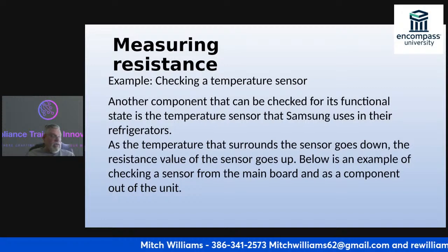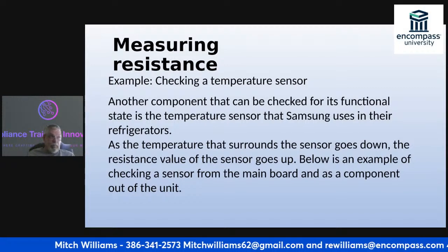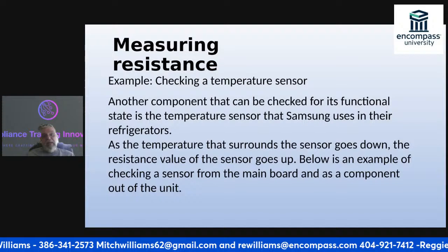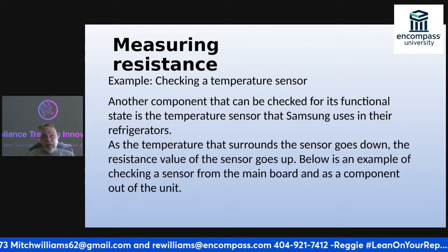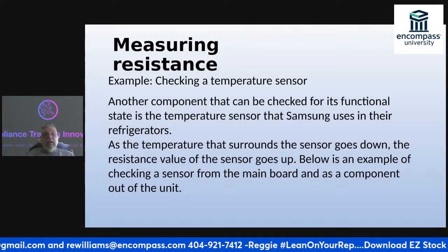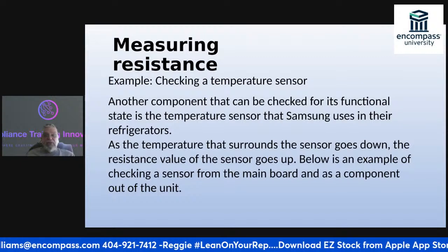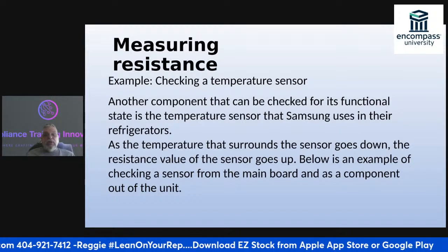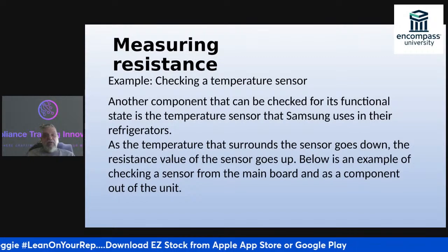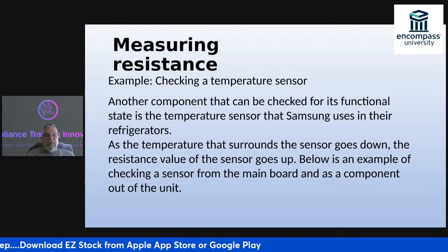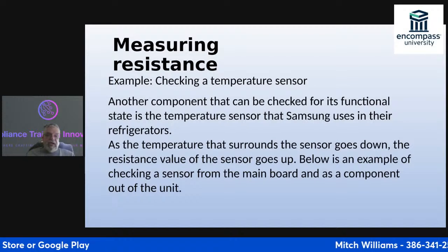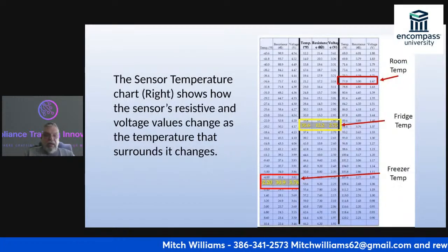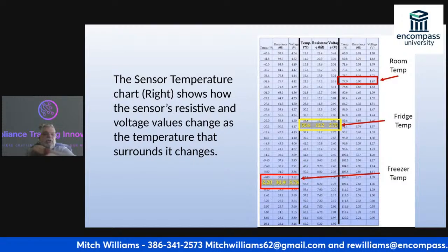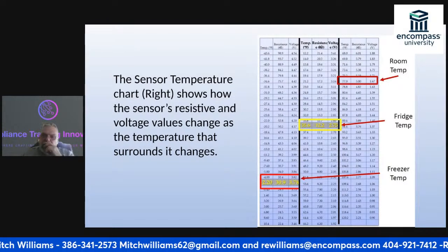Here's the interesting thing about the temperature sensor in a refrigerator. As the temperature that surrounds the sensor goes down, the resistance value of the sensor goes up. That's something that you need to remember. Below is an example of checking the sensor from the main board as a component out of the unit. So what I'm going to do is I'm going to check it.